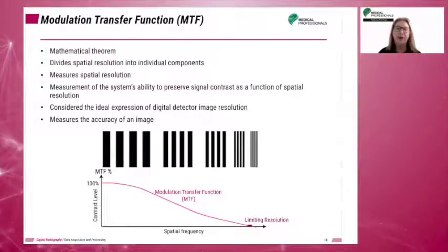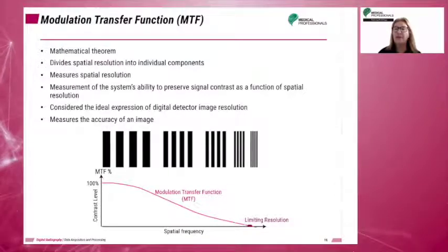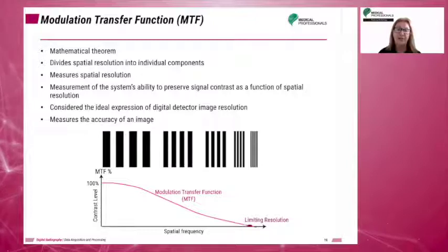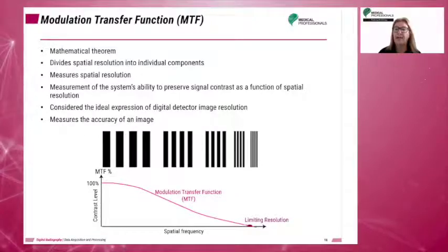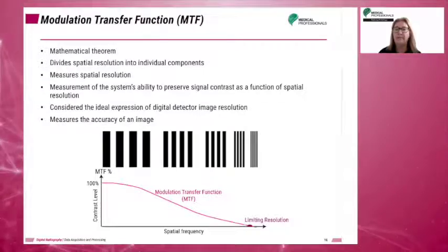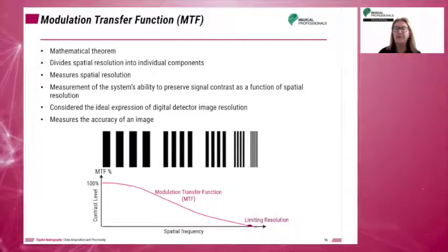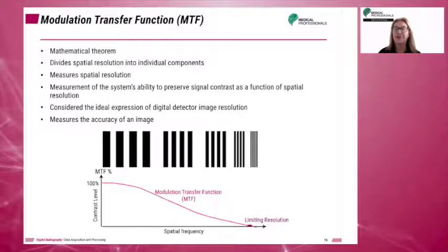According to Carlton and Adler, MTF measures the accuracy of an image compared to the original object on a scale of 0 to 1. A perfect image would have a value of 1. Higher MTF values at high spatial frequency are a key specification in digital detector design.